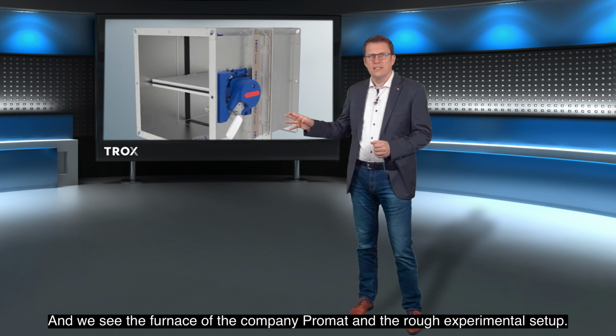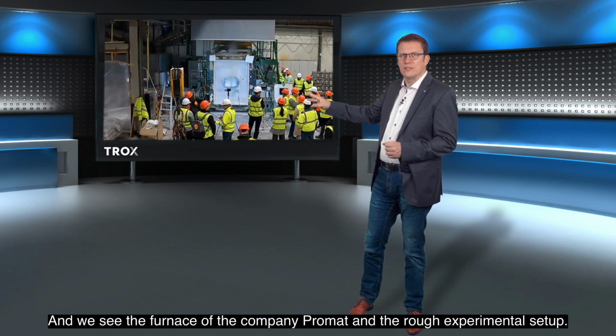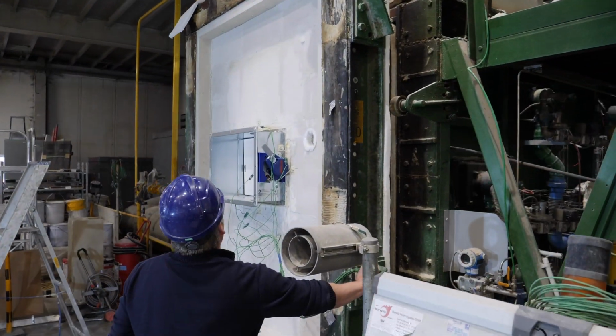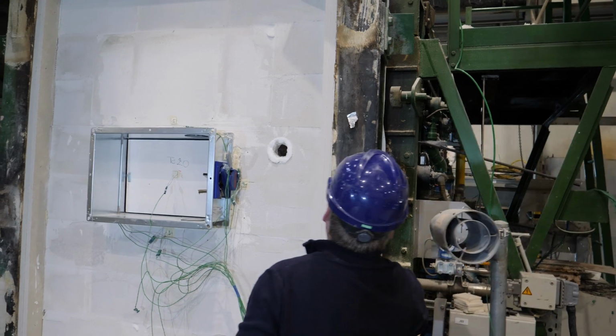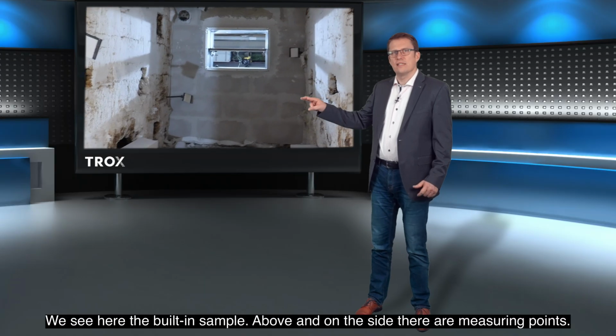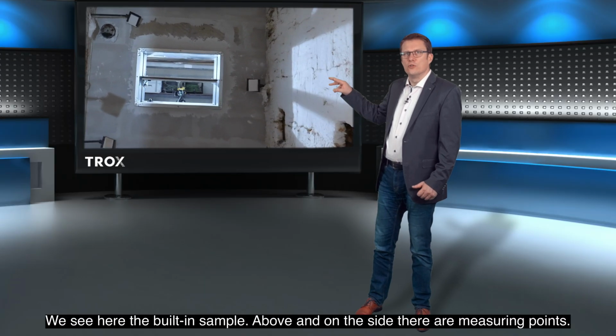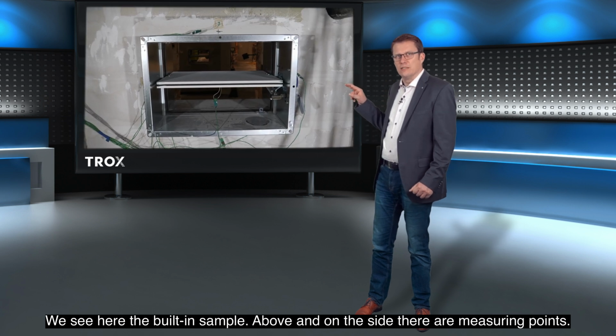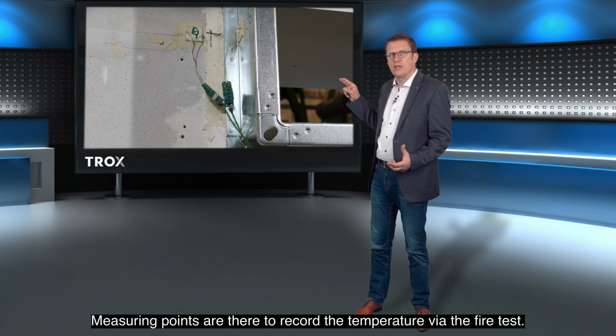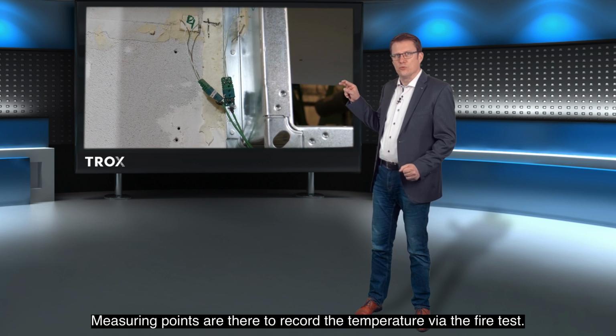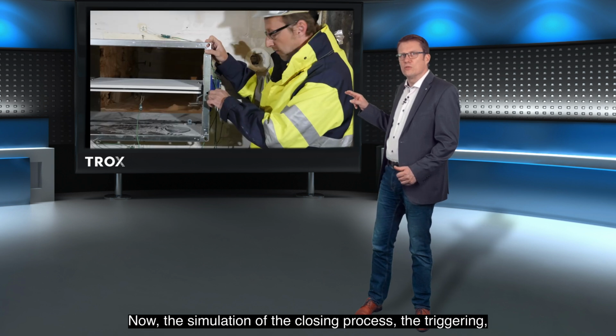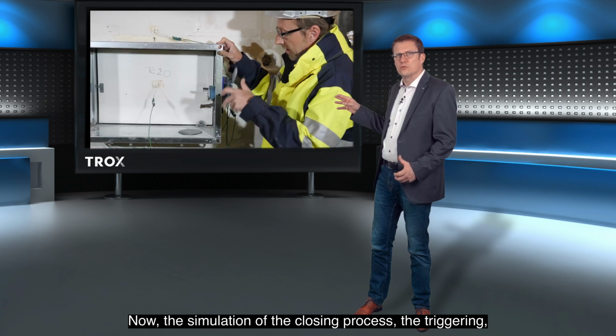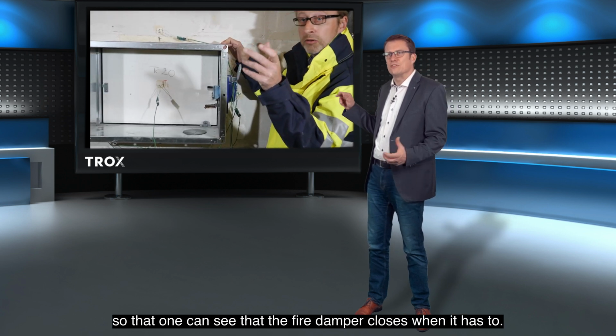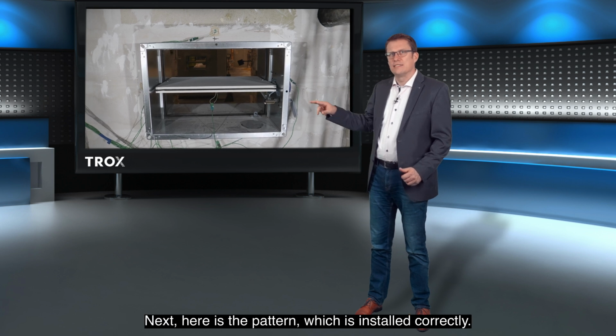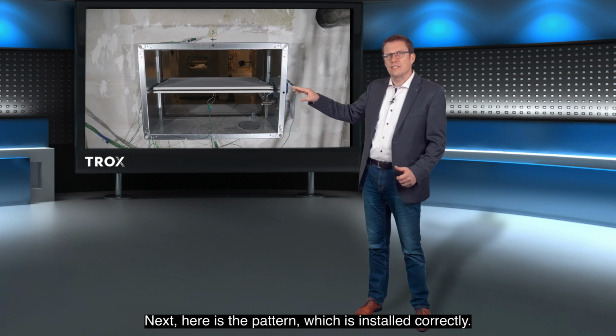And we see the furnace of the company Promat and the rough experimental setup. We see here the built-in sample. Above and on the side there are measuring points. Measuring points are there to record the temperature via the fire test. Now, the simulation of the closing process, the triggering, so that one can see that the fire damper closes when it has to.